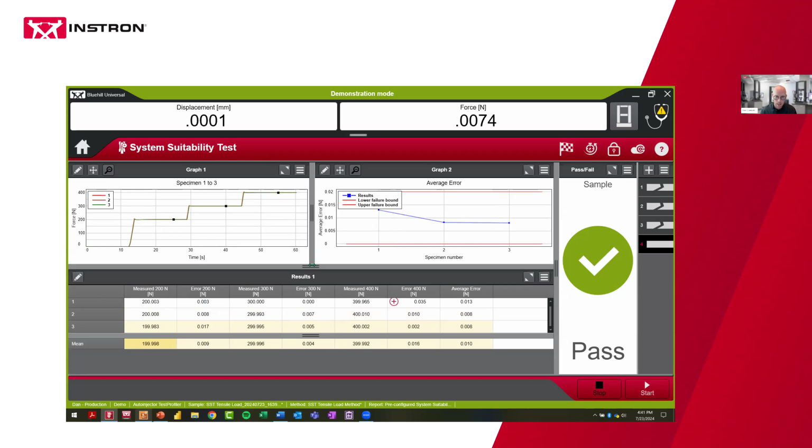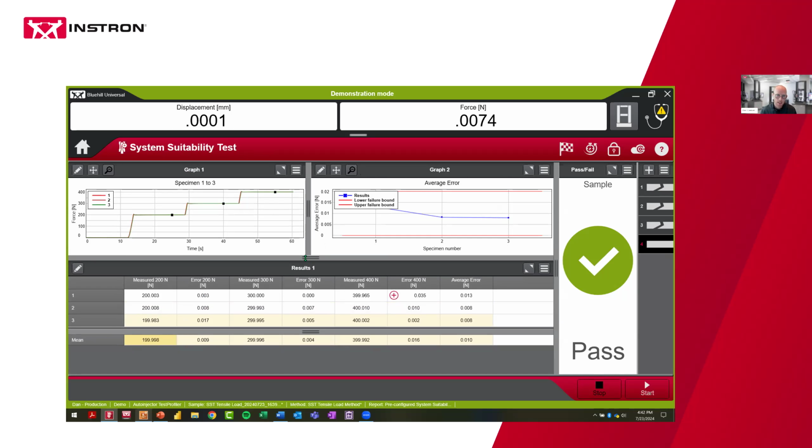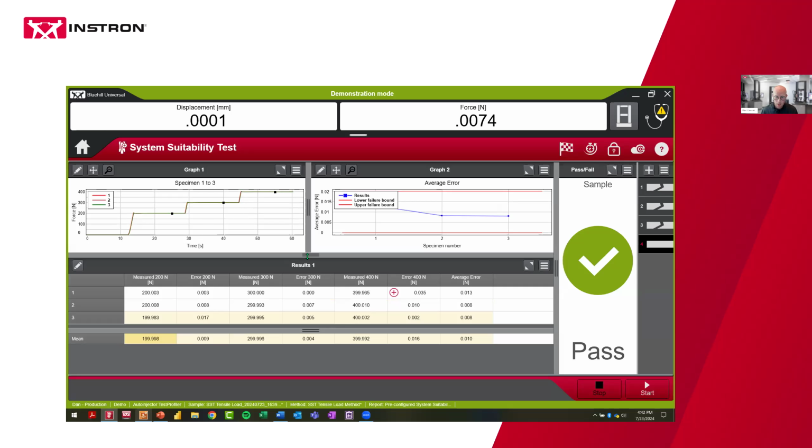It's going to be pre-configured in the method to say, hang dead weight ID 1234, and we'll know what you've configured that method's specific weight to be. Or if you had a spring constant, you could just use a spring constant and calculations to determine the value at any given point.